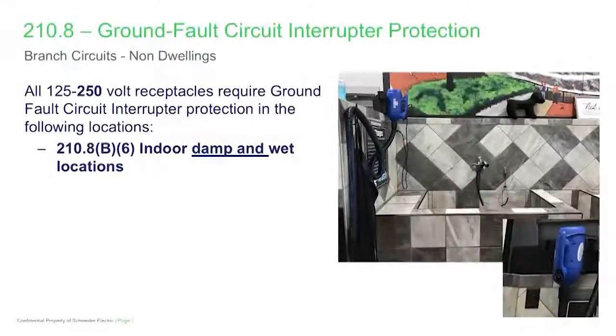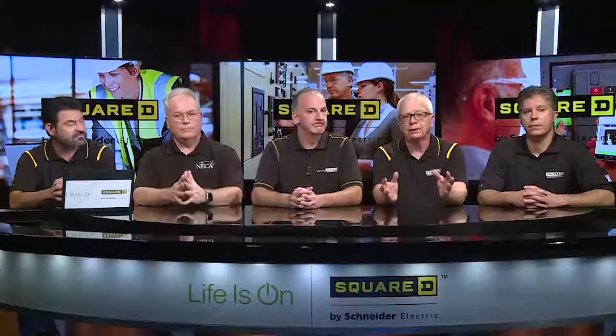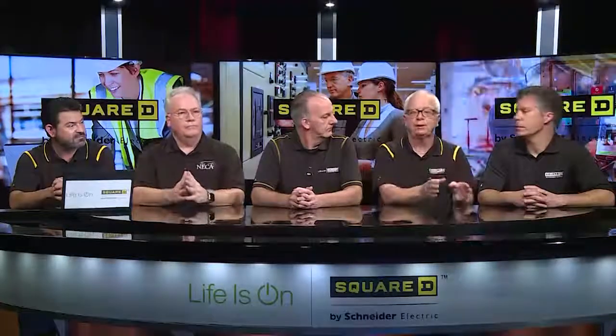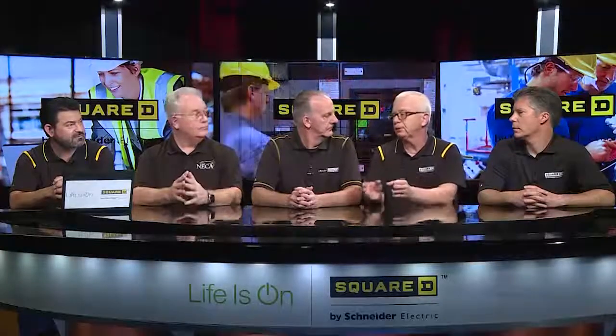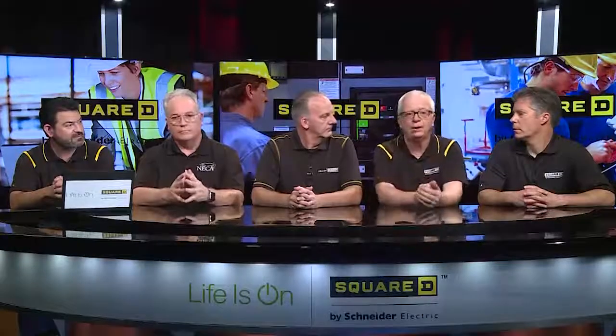The next area in this series of GFCI changes is adding damp to include both damp and wet location areas. Common areas you see today are locations where you have pet washing stations where you can reserve and self-wash, and there are receptacles in these areas for dryers and different appliances to be used. Damp and wet locations that are indoor will now clearly have GFCI protection because the hazard is the same. As we move on, what we're doing is continually identifying where those hazards exist.